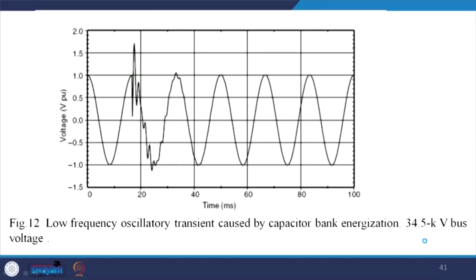Now, this is an example of a low frequency oscillatory transient caused by capacitor bank energization, at 34.5 kilovolt. You can see that this voltage is distorted, thereafter again it comes back to a smooth oscillatory waveform. So, we had a transitory oscillation because of the switching of the capacitor bank.